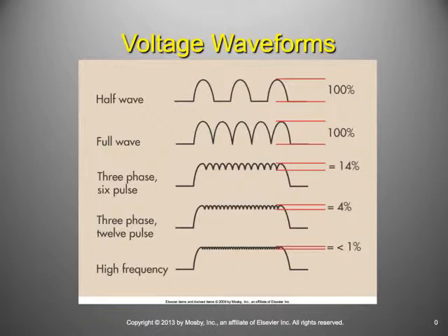And then high frequency, which is what we have in what we call the presidential suite, the bigger X-ray machine, has a high frequency. It's got like a less than 1% ripple in it. So when it comes time to make an X-ray, we're going to prefer the high frequency room for a number of reasons.